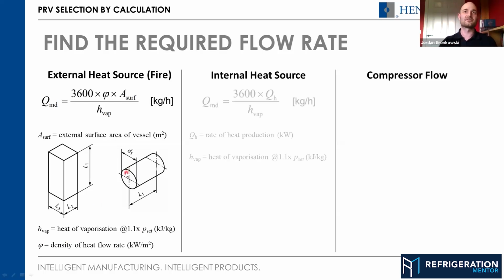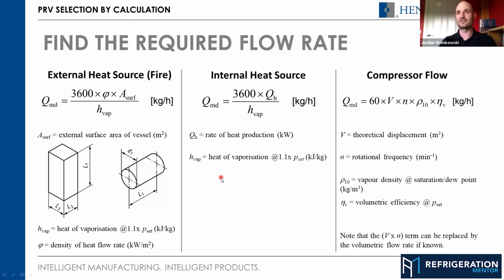Internal heat source, very similar equation, but you have the same heat of vaporization, and you also have this rate of heat production term, which again comes from the heating element or whatever you're using in that scenario. In compressor flow, really what this equation is doing is working out the flow rate of the compressor in kilograms per hour. You're looking at the volumetric flow, which is these terms taken together, multiplied by rho, the vapor density, and by the volumetric efficiency of the compressor.